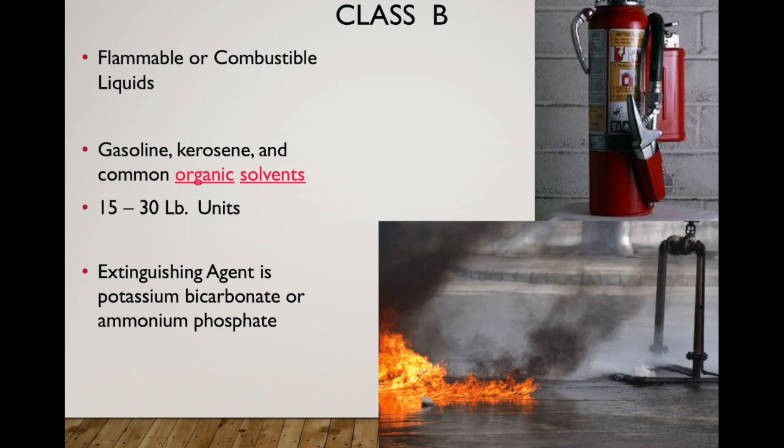Class B fires involve flammable or combustible liquids. The big difference there is just the temperature at which they ignite. We know gasoline is very volatile and ignites regularly, even in sub-zero temperatures. So that's a flammable liquid. Flammable liquids ignite under 100 degrees Fahrenheit and are basically dangerous all year long. Combustible liquids ignite over 100 degrees Fahrenheit and are less dangerous most of the time during the year, but both are in the Class B flammable or combustible liquids category.